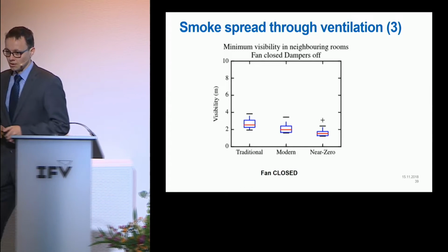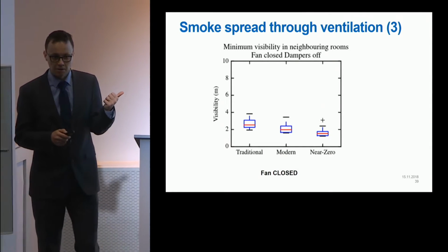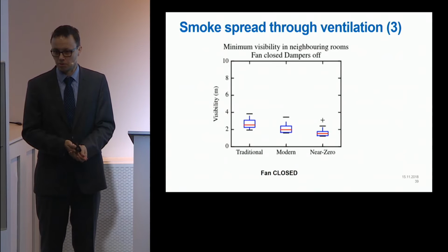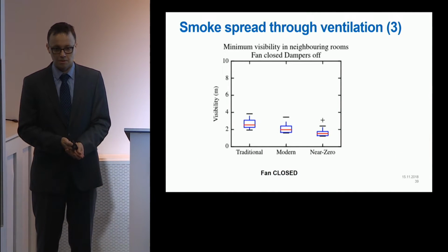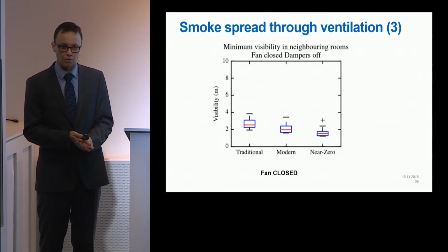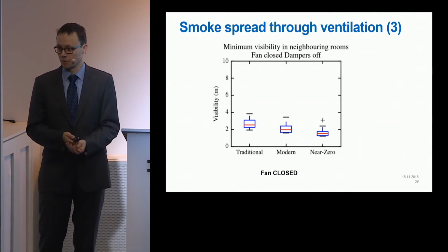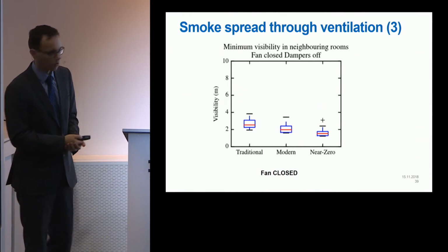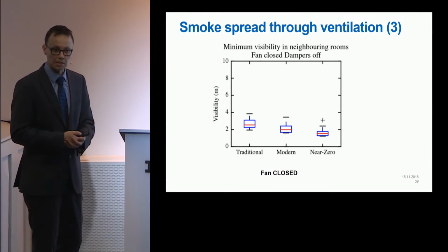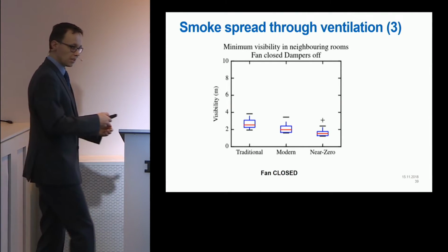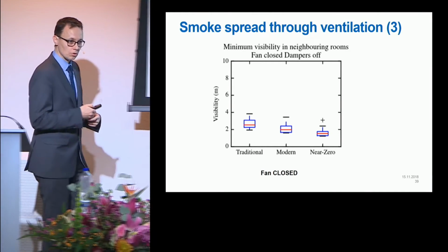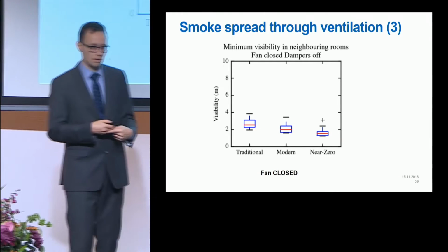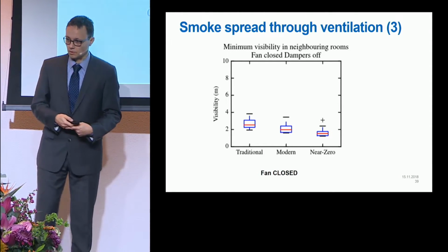Okay, so before the fire service requires that, in case of fire, stop the fans, it should make sure how it actually works. In case of emergency, you don't have time to find drawings and the operational logic of the air handling units. So it means that in our fire safety and ventilation designs, we should, in cooperation, look at how these things should be designed in order to make sure that they work safely.